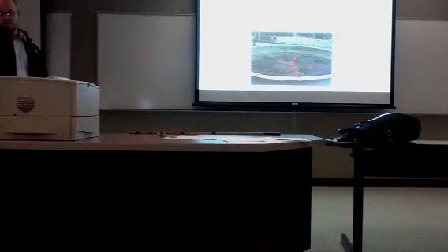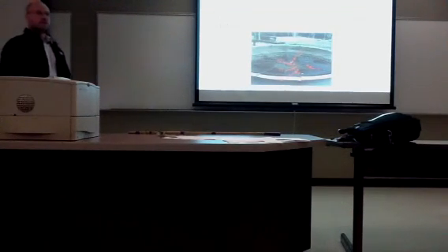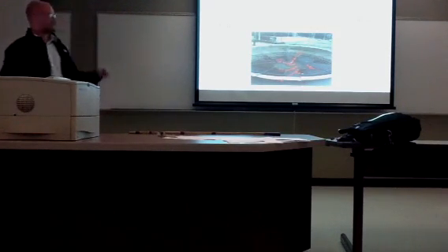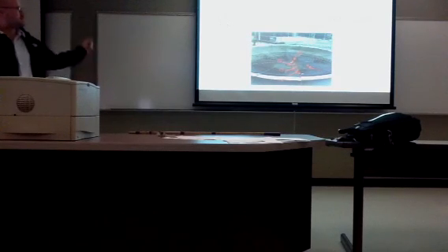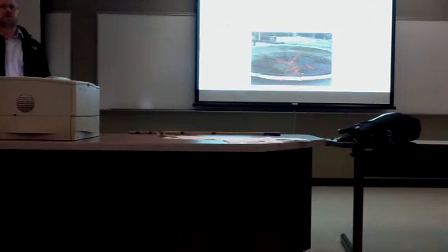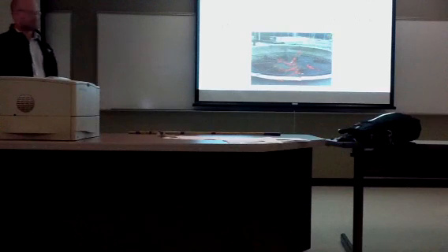Conclusion and recommendations. Since we only collected exhaust temperatures at one location along the radius of the fan, that doesn't show how the temperature is affected by the flow rate across the radius, because the velocity profile does change. So I'd recommend taking more temperature measurements across the radius of the fan. And then we only took velocity measurements across one angle, so we might want to try other angles relative to north.